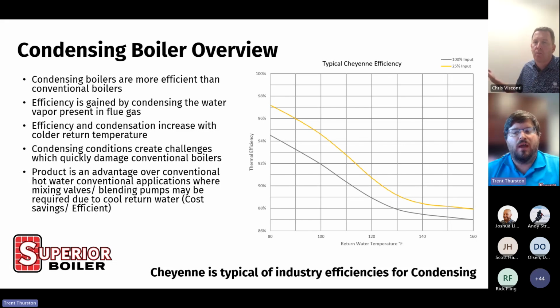One of the things that we do have is we can have a large delta T. With conventional boilers, you'll need blend pumps to minimize temperature differential across the supply and return. And with condensing boilers, we actually like the large delta T because it allows us to get a colder water temperature. So it simplifies your piping arrangement. Now, as we can see on this graph on the right, to get the good efficiency that we're looking for, we do need cold water coming back to the boiler. At higher temperatures, you will not see any condensation, and your efficiency is basically the same as a conventional boiler.